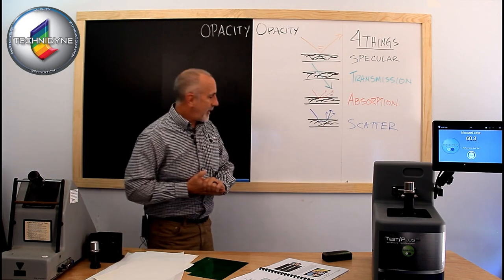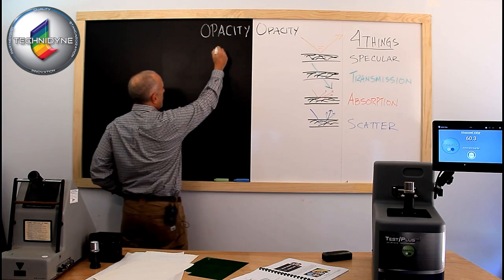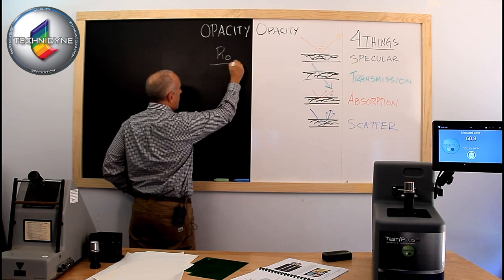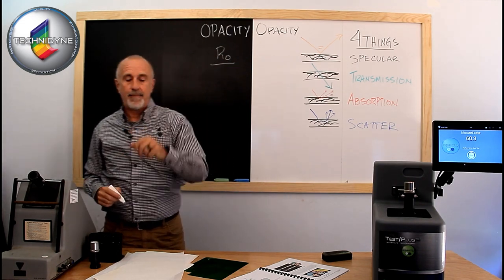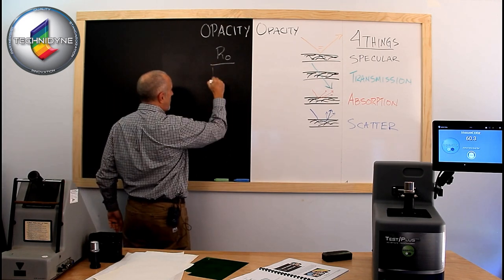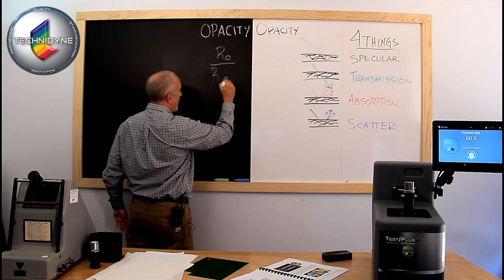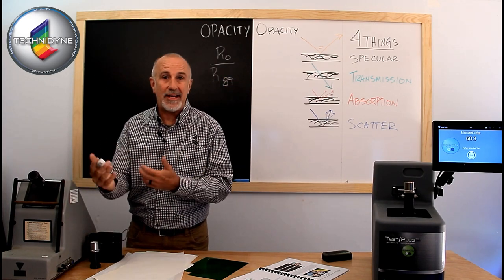So they came up with a calculation. So you would make a measurement, and you would get what they called R0. And R0 would be that single sheet of paper backed by the black cup. And you would then measure that same single sheet of paper when it's backed by the white backing, which had a reflectance of 89%. So they called that R89.